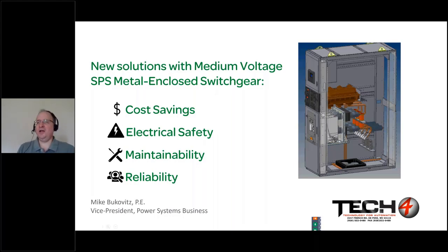We improve maintainability. When I say improve maintainability, it's not a minor improvement. The recommendation for the circuit breakers I'm showing you here under quote unquote normal condition applications is once every 10 years. So that's an order of magnitude of 3 times less than the standard Factory Mutual or NFPA 70B recommendations for medium voltage circuit breakers, as well as reliability. One of the breakers I'm going to show you today is rated for 10,000 mechanical operations, and the other is rated for, hold on to your seats here, 30,000 full load break operations. Absolutely incredible, the advances in technology and performance with respect to safety, maintainability, and reliability.